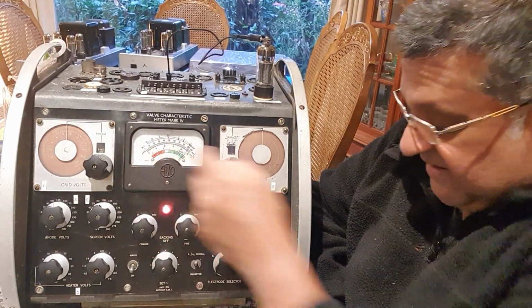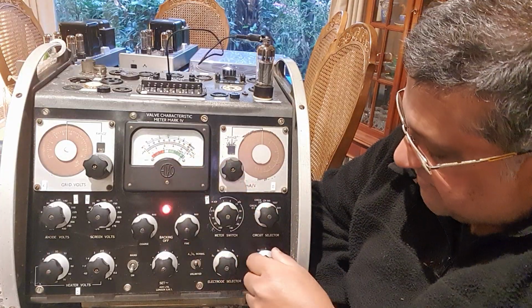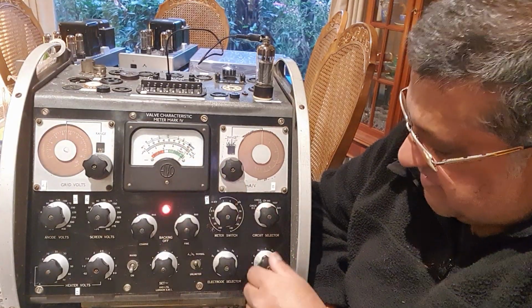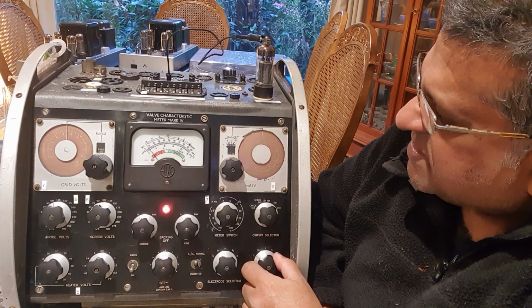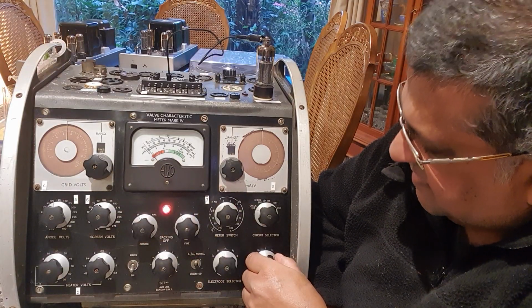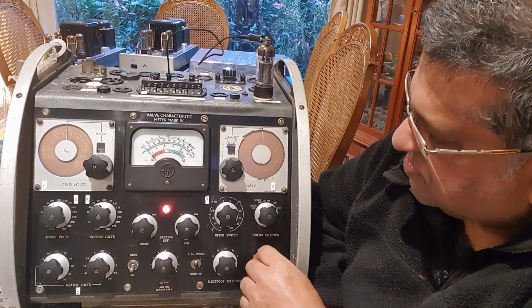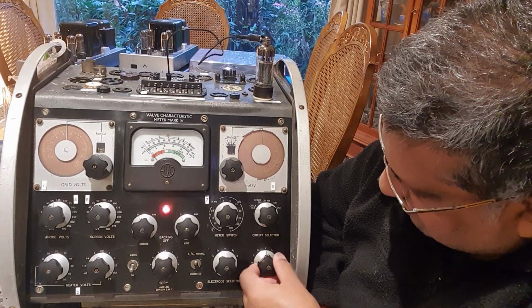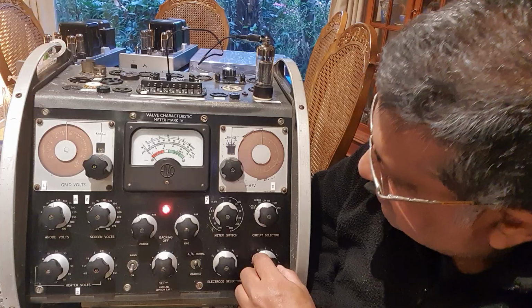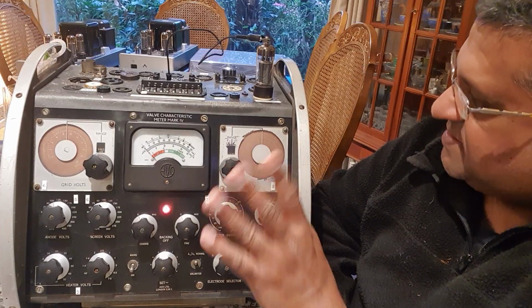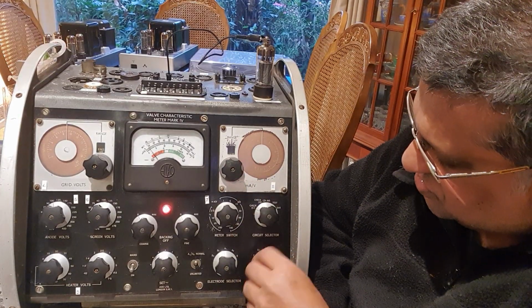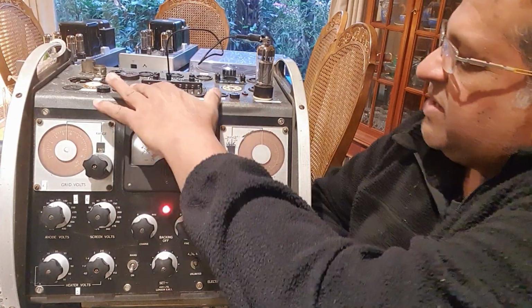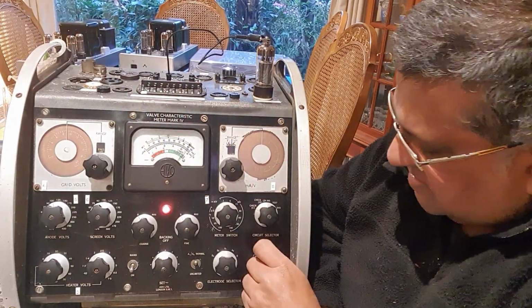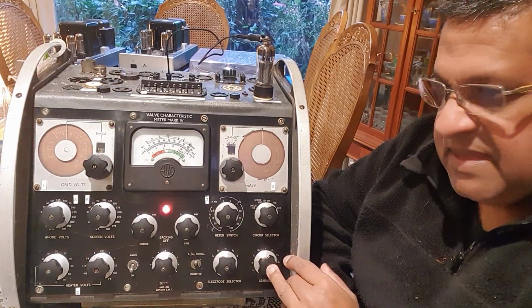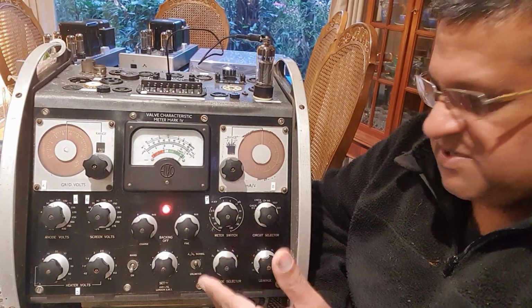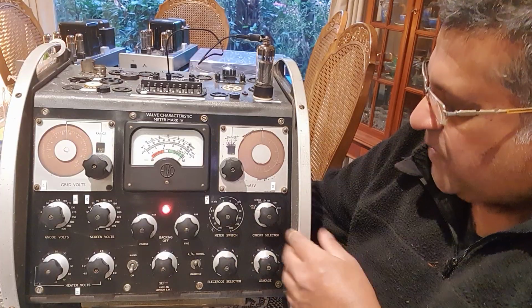This has to be on the left-hand side. As you can see now, as soon as I put it to cathode, the meter will deflect to the left. So this basically is, there's no connectivity there, there's no shorts on the grid, there's no short on the screen, there's no short on the anodes, and so on and so forth. It's zeroed, right? Which also shows that the correct wheel settings are set for the correct valve, right? We put it back here. Now we can begin the first process of testing the valve.